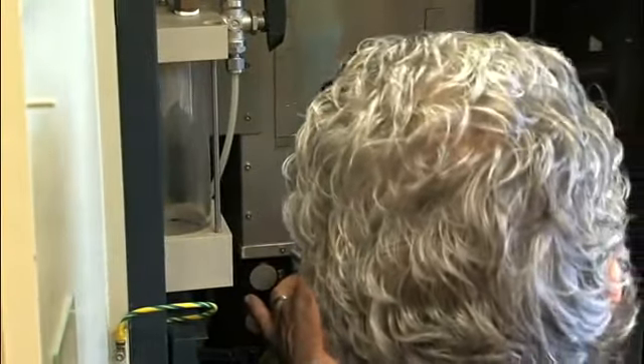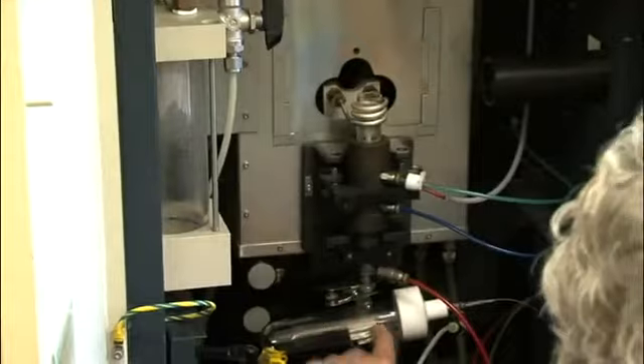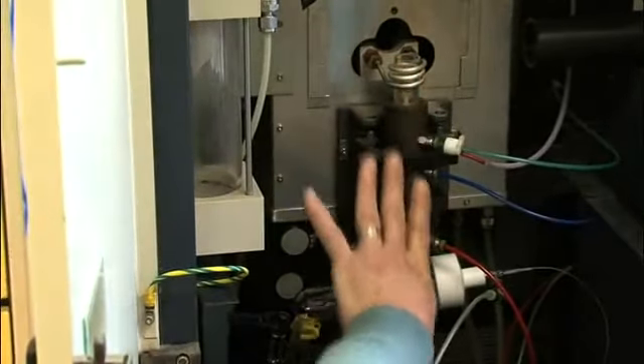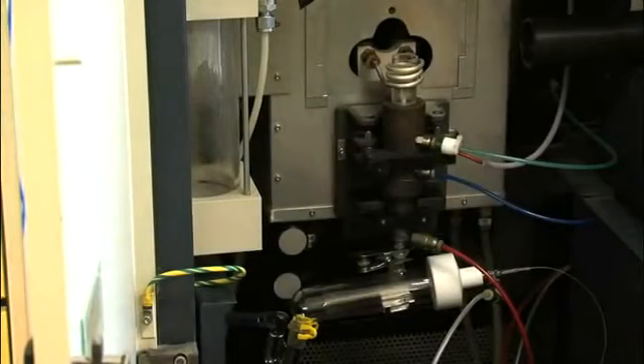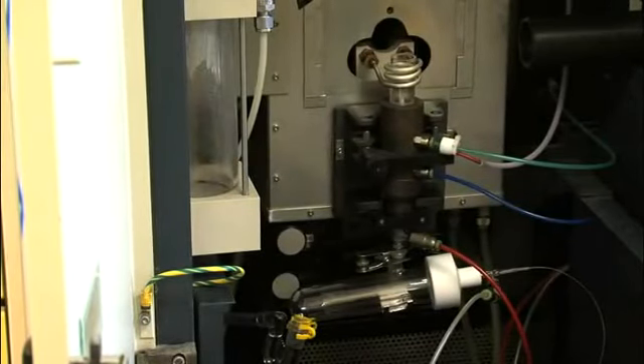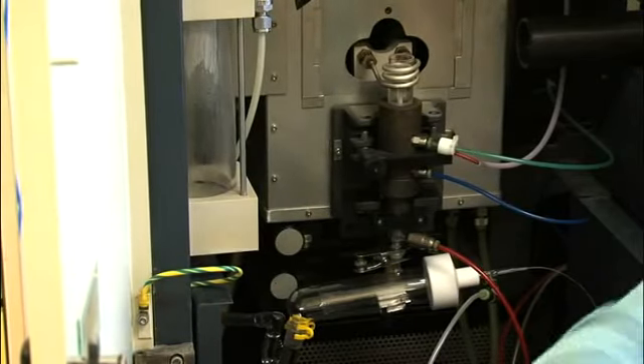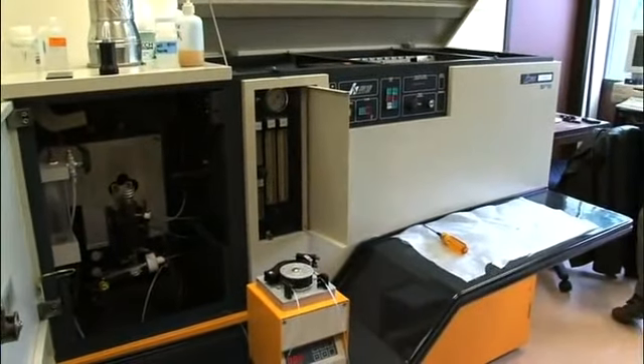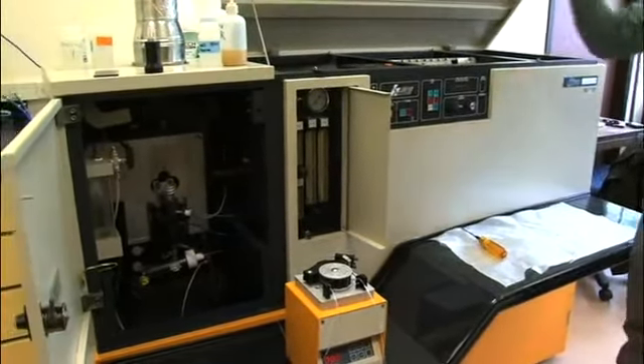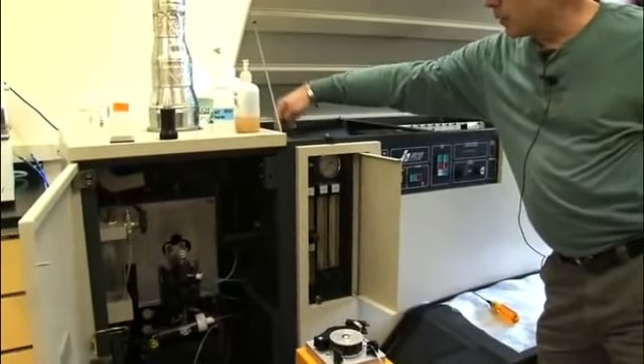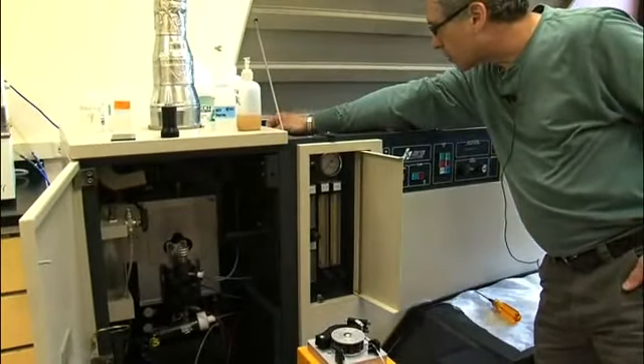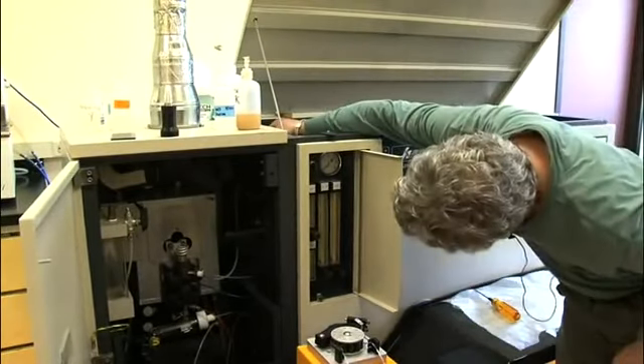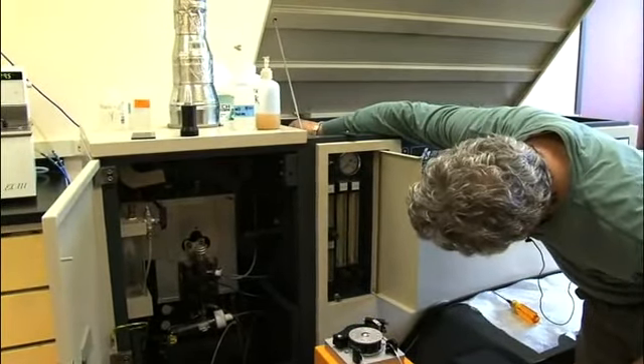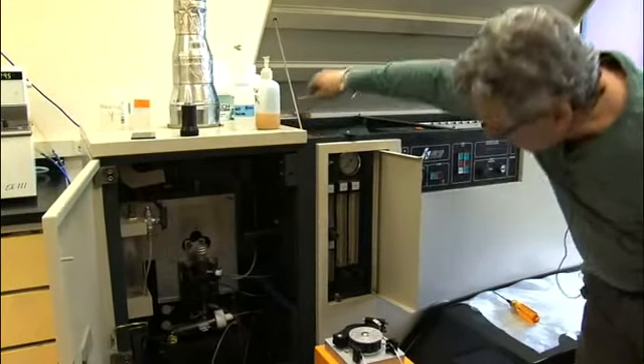This is called a sheath gas. What this does is it mixes with your nebulizer carrier gas. It's just a gas that's always used. I don't know what the main purpose of it was, but okay, so 12. Your G1 should be 0.2. It's a little high. The adjustments are all preset with electro valves, which are all labeled right inside here. So I'm gonna just lower that G1 gas a little bit. Use the center of the ball.